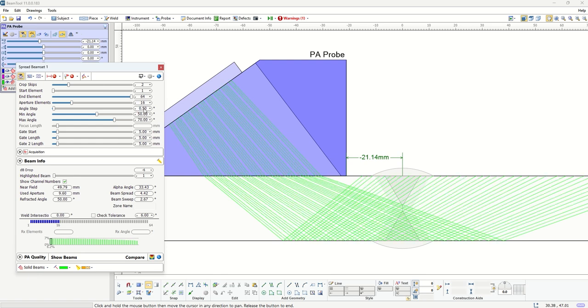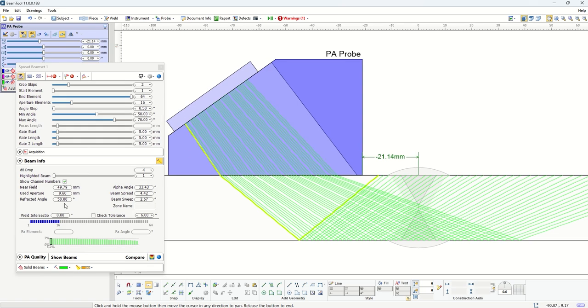What you will notice now is if I turn on this option here, which is highlighting the beams, as you move this highlighter, all information with respect to the beam that is being generated is presented here. So the information that we have is what aperture is generating the beam, what is the angle of the beam, what is the near field, or basically what is the incident angle in the piece. And what I want you to pay attention to is that as I move through these beams, first you notice what angles we have, and also what aperture is being used. So the first beam, which is the 50-degree that I chose, is generated by the first 16 elements because I chose the start element to be 1 and the aperture to be 16. Now, if I keep moving, you notice that I'm in the next beam, which is 50.5, but this beam is now being generated by aperture from 2 to 17.